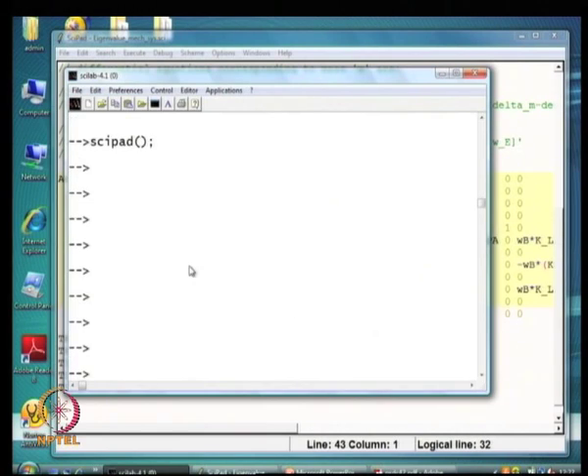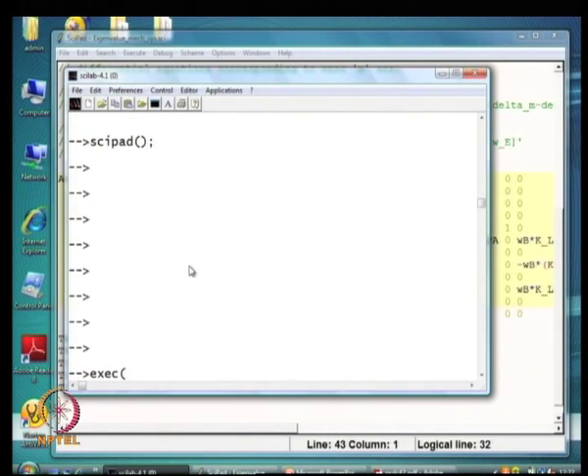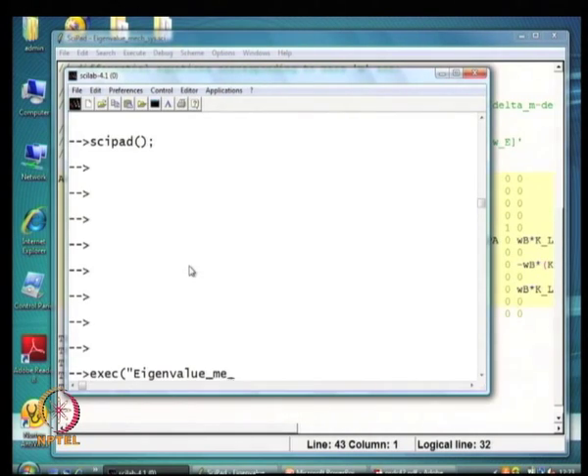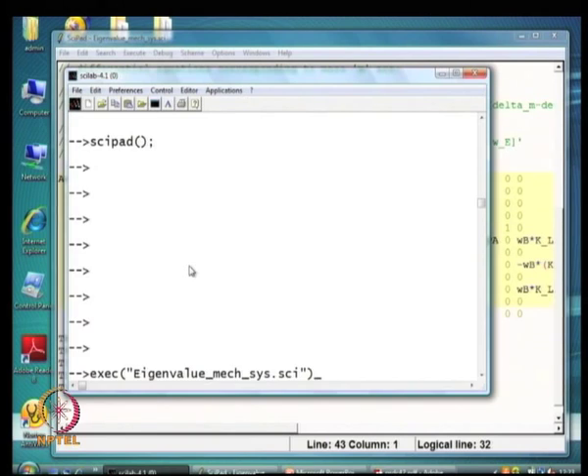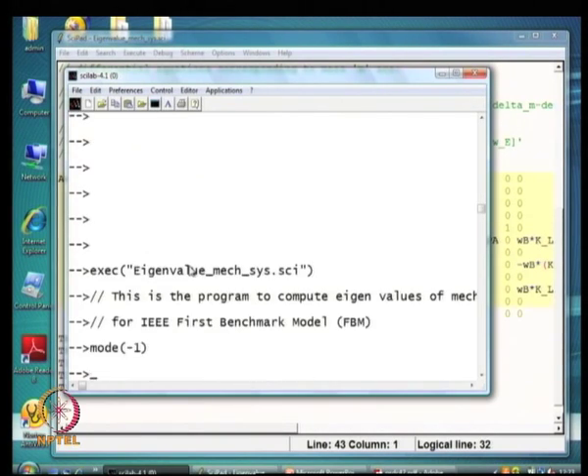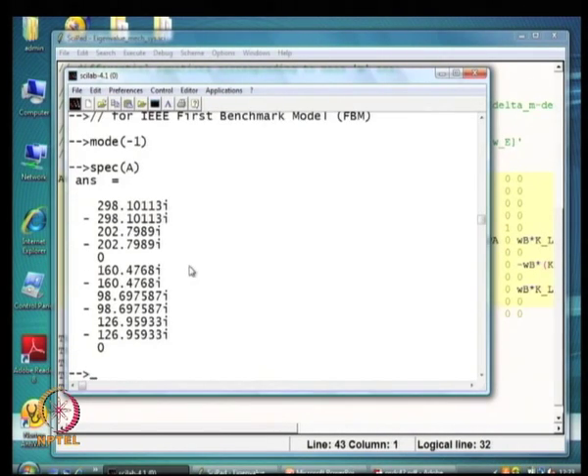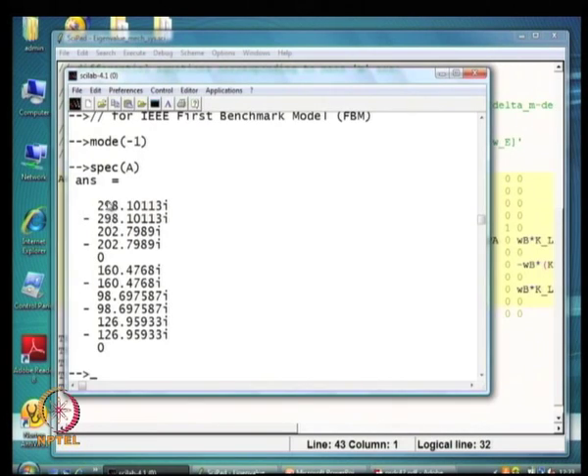We will run this program and form the A matrix of the mechanical system in isolation assuming electrical torque is zero or constant. Taking out the eigenvalues, the eigenvalues are in radian per second. There are basically six pairs of eigenvalues — five of them are torsional oscillatory modes. If we divide by 2*pi this gives the frequency of these oscillations.